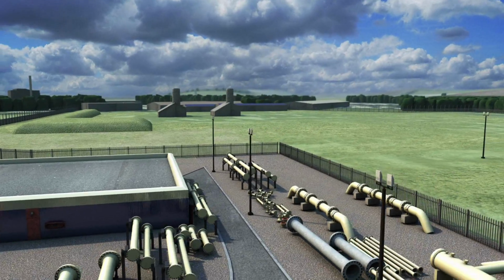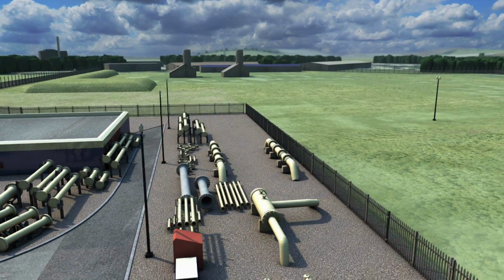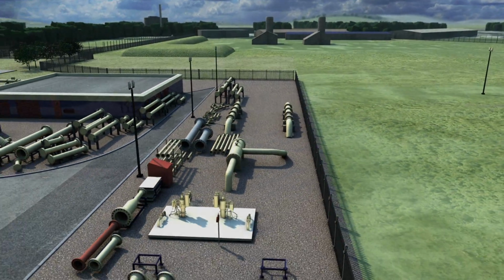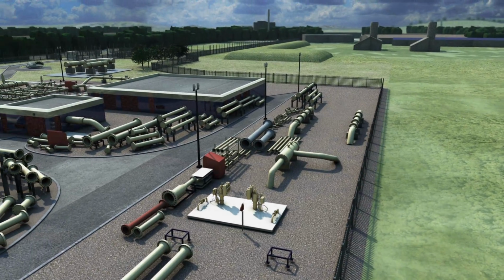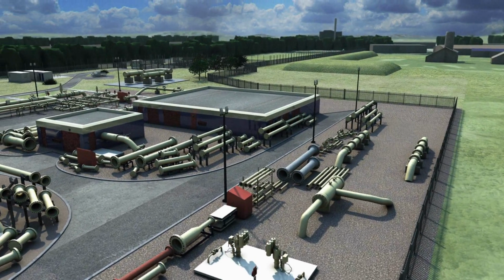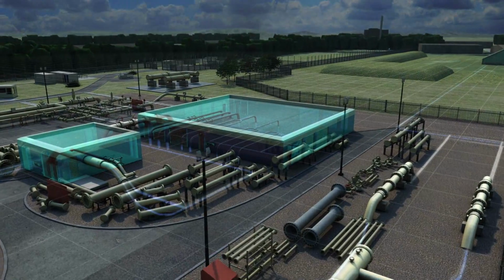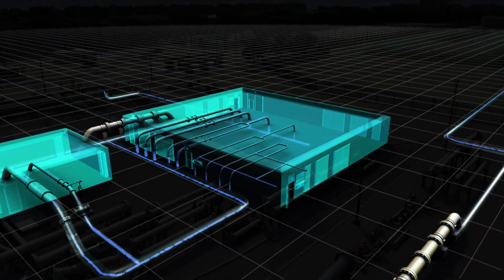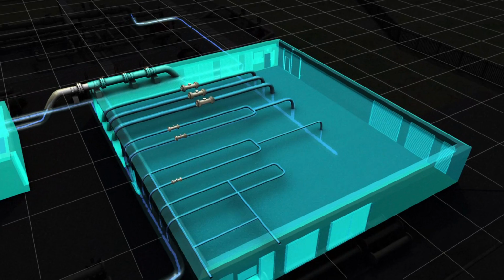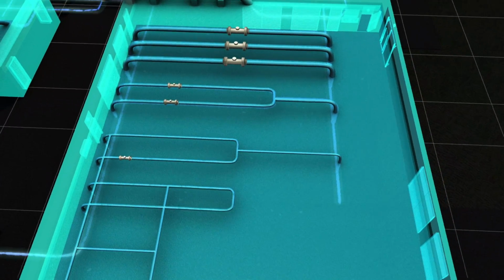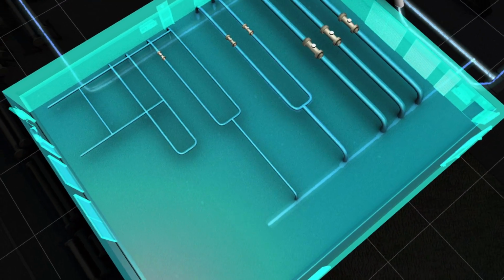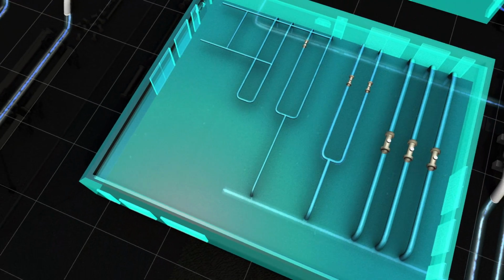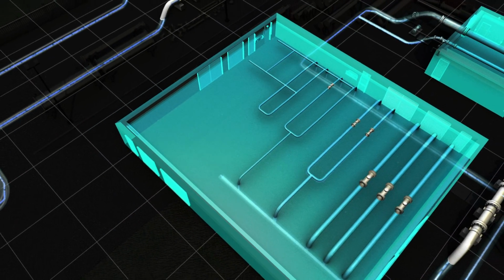High-pressure gas enters the secure flow center site through two slam-shut safety valves. The gas then flows into the meter house through six reference turbine meters, which are independently calibrated to traceable international standards. Customers' smaller diameter meters, from 1 inch up to 8 inches, are also calibrated in this building.